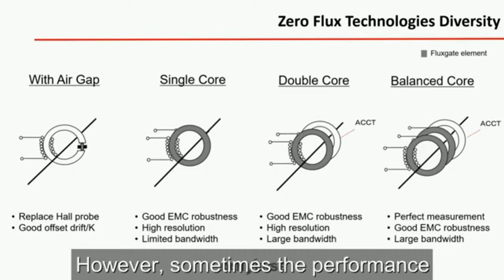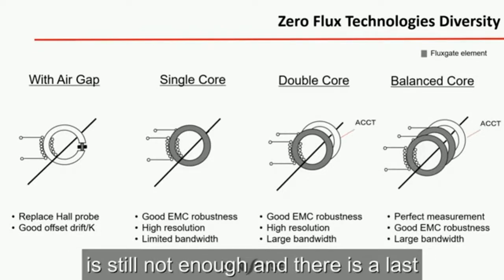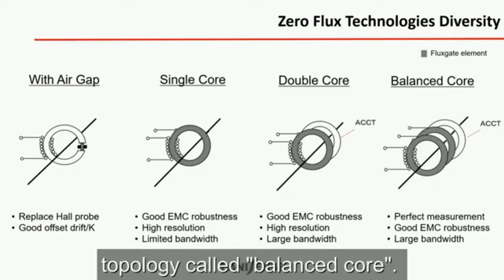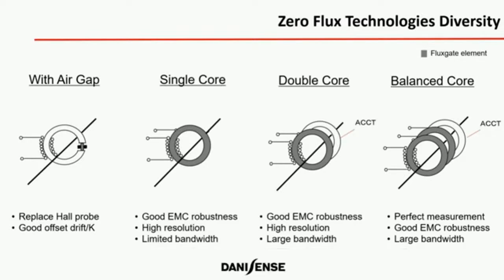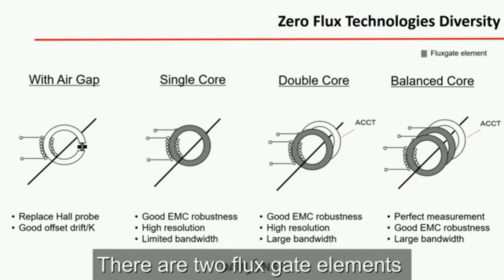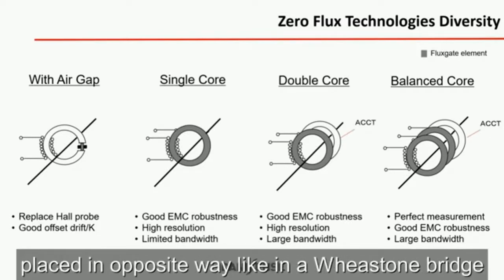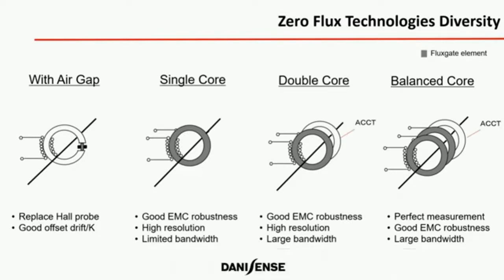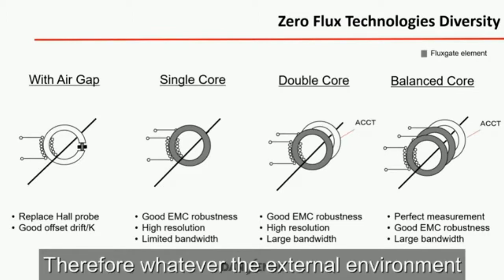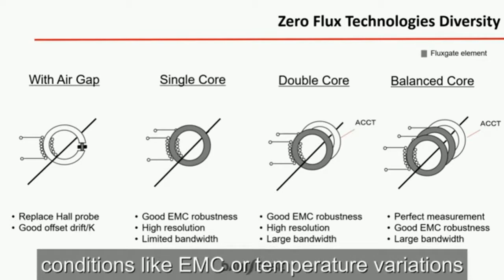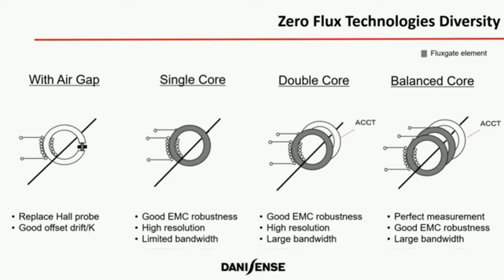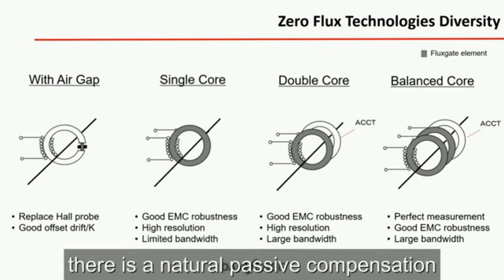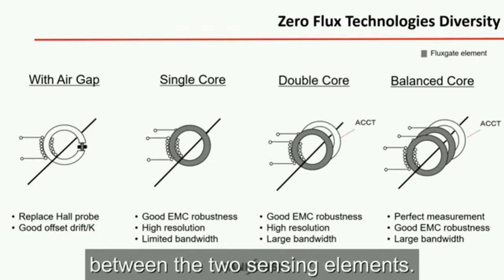However, sometimes the performance is still not enough, and there is a last topology called balanced core. Here, there are two FluxGate elements placed in opposite ways, like in a Wheatstone bridge. Therefore, whatever the external environment condition, like EMC or temperature variation, there is a natural passive compensation between the two sensing elements.